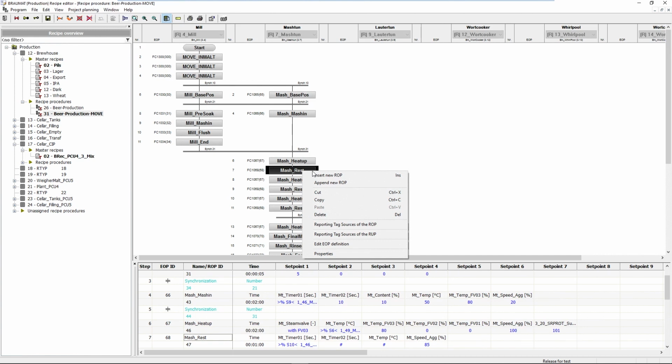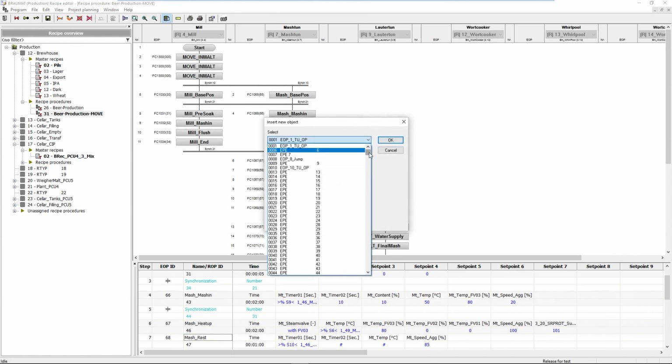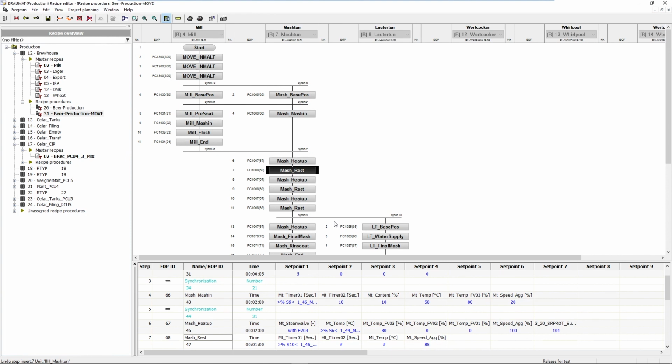As already mentioned, we can select the steps with corresponding names from a prepared pool of steps. Furthermore, we can connect corresponding units, i.e. the aggregates within a system by means of synchronization. These synchronizations serve on the one hand to start a second unit from an existing timer position, or to artificially introduce a waiting time at the corresponding synchronization points until these two units are synchronized again. The advantage? These synchronizations do run on the server, not in the AS. This makes the procedure extremely transparent.